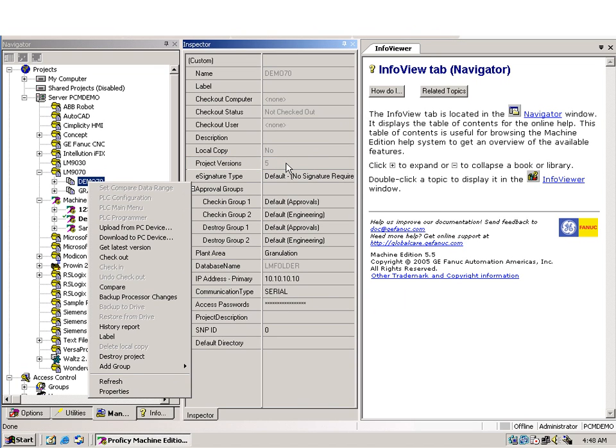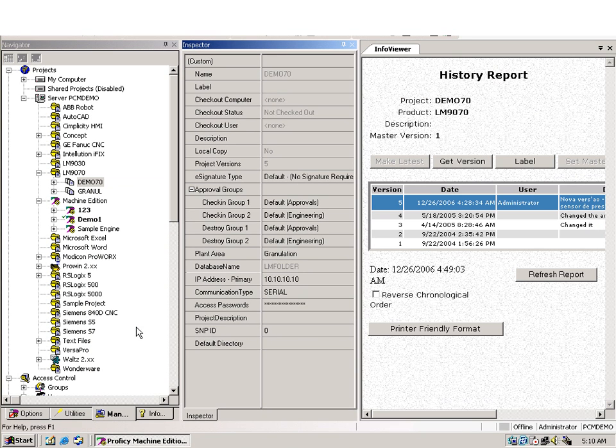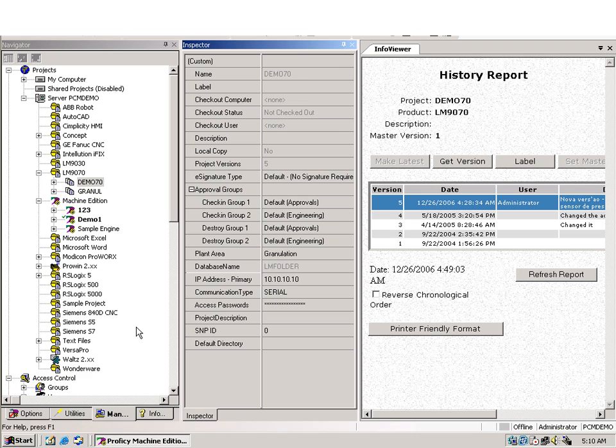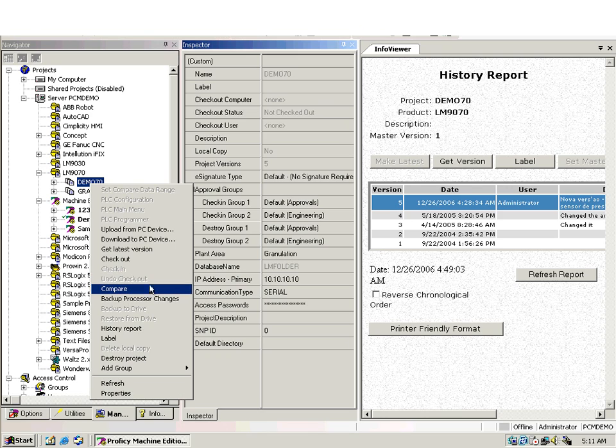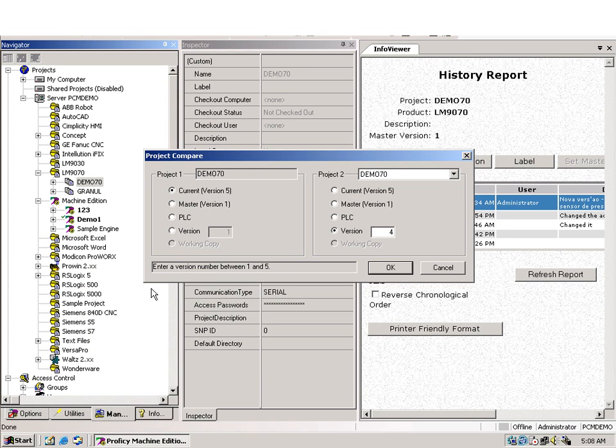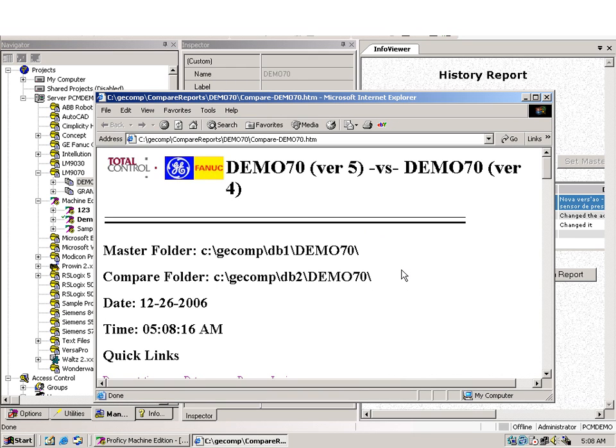We can also get a history report, and with that we show all the versions stored on the server. No more need to keep a bunch of diskettes or know where was saved the particular version. Let's now show a very useful feature, version compare. Here we can compare versions with other versions, or versions on the server with the PLC. And here is an HTML report with the differences found. We can easily see now the coil present in one version and not in the other.